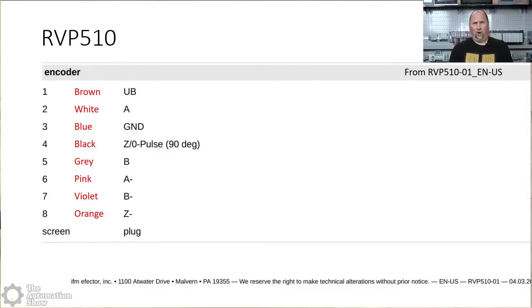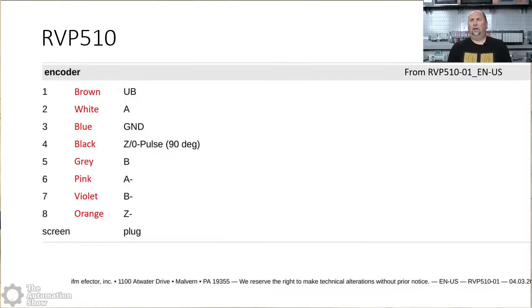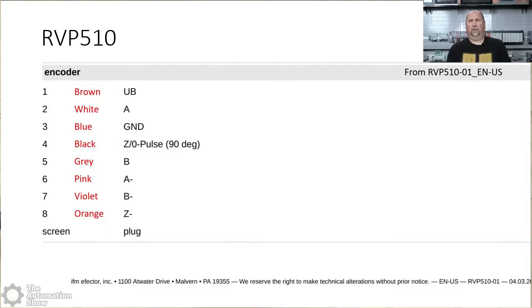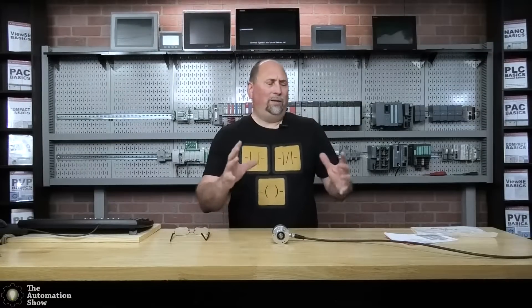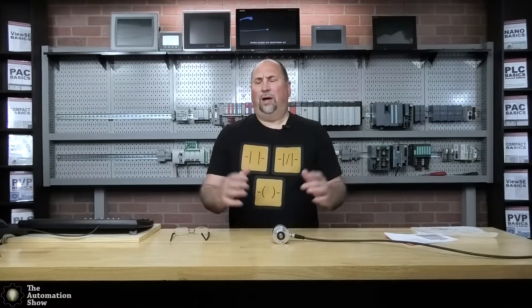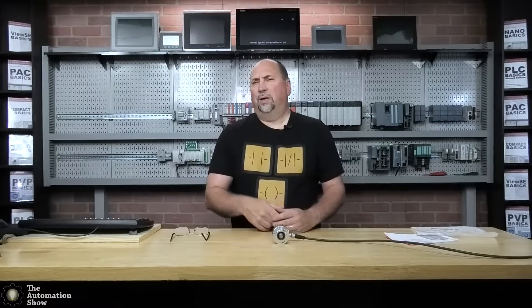And two is white. And that is your A signal from the encoder. Three is blue, which is ground. Again, blue is typically DC negative or ground. Four is black and that's the Z pulse. And then five is gray and that's B and so on.